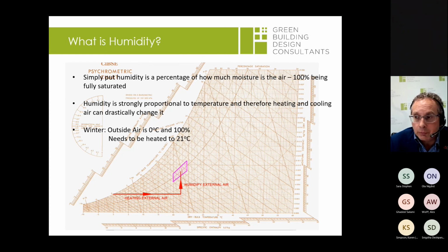They were silver with a red stripe down the side. Water went into one side, with electrical element heaters in the middle, and inside were bottles a bit like kettles, constantly boiling. Steam from the top of the kettle went through pipes into a controlled environment inside the AHU. After heating, you'd add humidity to the air to reach about 50%, plus or minus, in line with CIBSE guidance for good office environments back then.